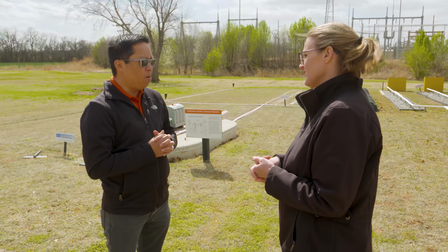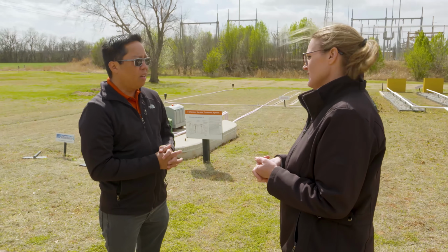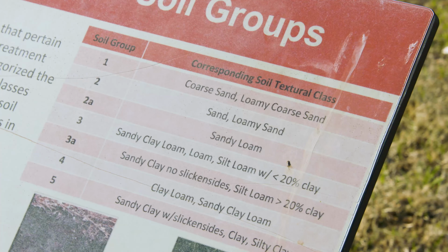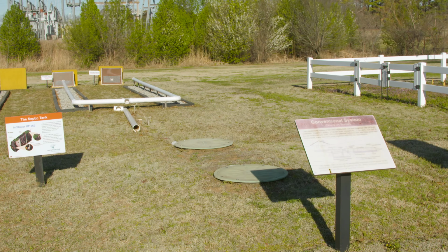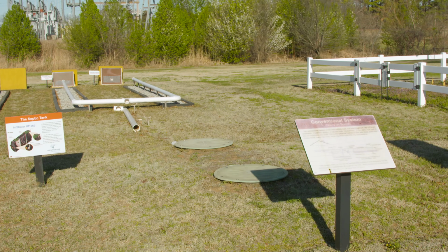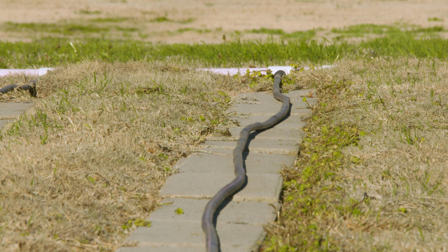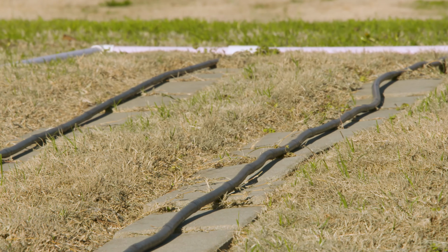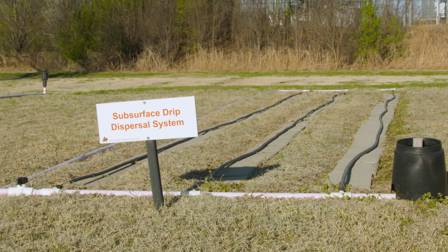The other thing is you don't want to run anything that is very heavy in your backyard, where you spray this stuff, right? Because compaction of the soil means what? It means a soil that does not allow infiltration of water. Right. So if you have ponded effluent on the surface, that's not very good, because that could run off to your neighbor or run up to your garden that has vegetables on it. So it's best to know where these lines and the spray heads are, because if you have to do some minimal earthworking, you want to avoid those areas, because you don't want to dig deep enough and cut some of the lines. Those drip lines could easily be cut by simple earthworking.